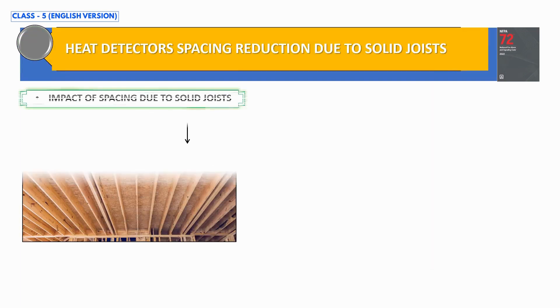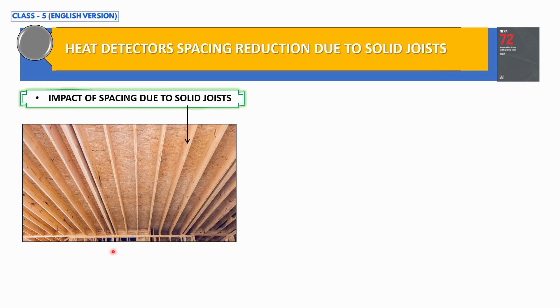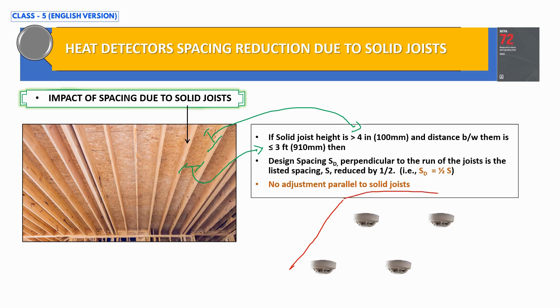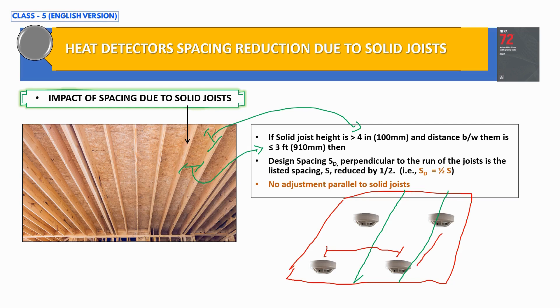Coming back to today's topic: the impact of heat detector spacing due to solid joist construction. As per NFPA 72, the design spacing of heat detectors is calculated using a specific formula if the solid joist height is more than 4 inches and the distance between solid joists is less than or equal to 3 feet. We need to know the distance between heat detectors both horizontally and parallel to the solid joists.